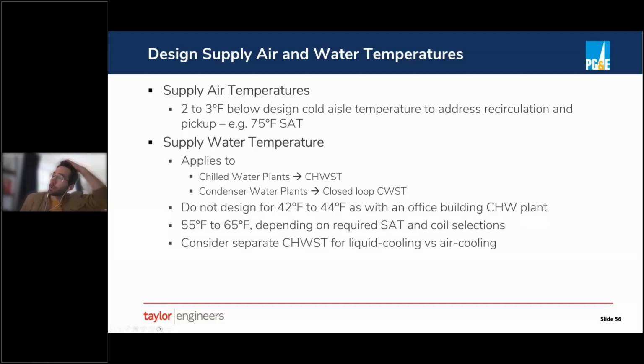So if we're looking at a chilled water plant, we're controlling a chilled water supply temperature. If we're looking at what we'll call a condenser water plant that serves closed condenser water to air handlers, then we're targeting a designed condenser water supply temperature. One common mistake that was made many years ago, we see it less frequently now, was that designers would design their chilled water plants for 42 or 44 degrees Fahrenheit at chilled water supply the same way they would for a chilled water plant serving an office building. But in an office building, you're trying to make air that's between 55 and 65 degrees. As we just talked about in the preceding example, I might be trying to make 75 degree air. So if I'm trying to make 75 degree air, I don't really need 42 degree water to do that. I can effectively make 75 degree air with 60 degree water, maybe even 65 degree water. And the warmer I make my chilled water supply temperature, the more efficient those chillers are going to operate. And if it's a data center where I have a waterside economizer, the more waterside economizer hours I'll get as well.